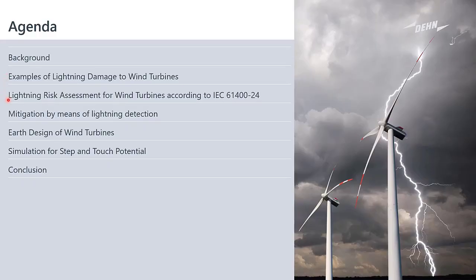From that, we will discuss lightning risk assessment. Now, this is a very, very important part of the whole webinar: there is a standard for doing lightning risk assessment. It's an IEC standard called 62305 Part 2. This is the main standard for doing risk assessments, but it's focused on structures and buildings. This is not always applicable to something like a PV plant or special cases such as wind turbines.